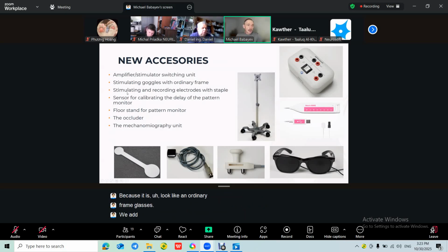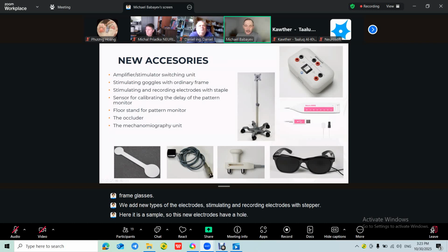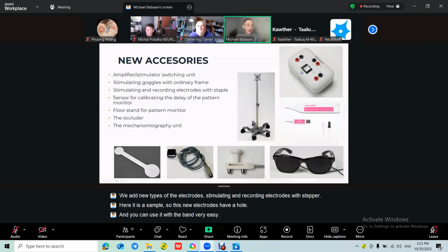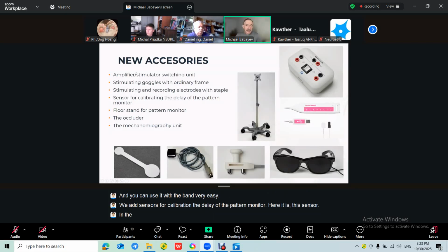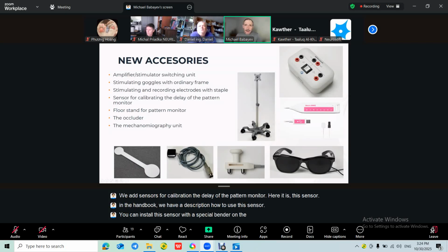We add new types of electrodes, stimulating and recording electrodes with staple. Here it is a sample. So these new electrodes have a hole and you can use them with the band very easily. We add a sensor for calibrating the delay of the pattern monitor. Here it is, this sensor. In the handbook we have a description of how to use this sensor. You can install this sensor with a special band on the monitor and make calibration. Maybe you know that the calibration of modern LCD monitors is very important, so that the values of the latencies will be valid. We add a floor stand for the pattern monitor, this floor stand. Now it is not necessary to look for some table. For the monitor, you can use this floor stand and install the pattern monitor.